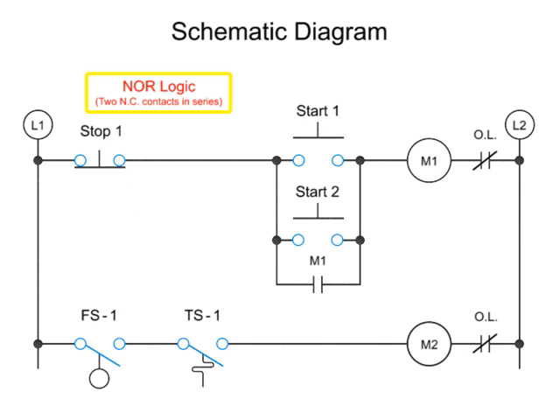NOR logic, an extension of NOT logic, operates by the inclusion of a second, normally closed push button in series. In this arrangement, pushing stop button 1 or stop button 2, the M1 coil is shut off and the M1 holding contact is deactivated.